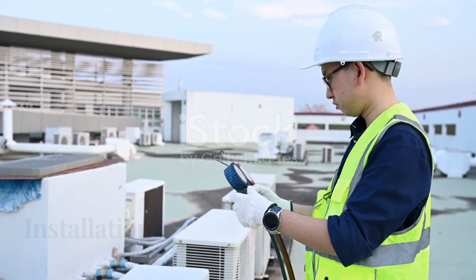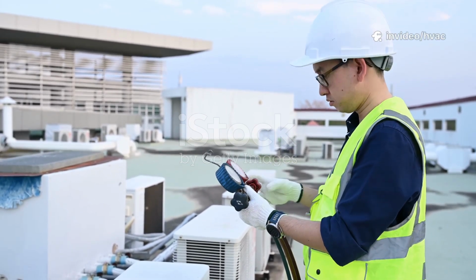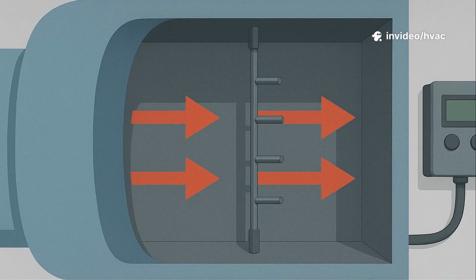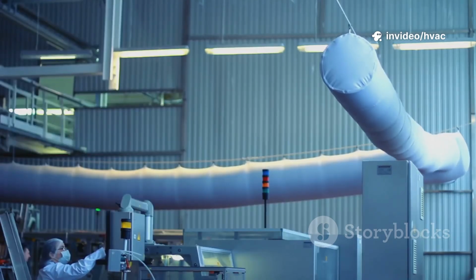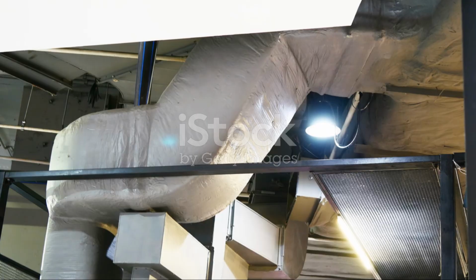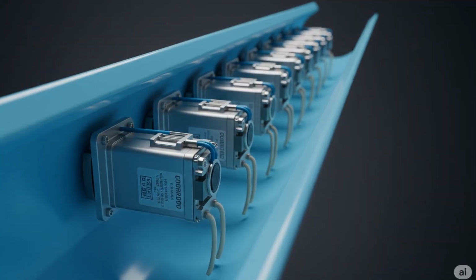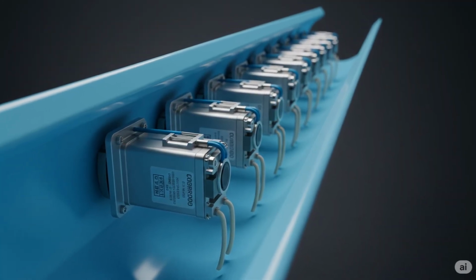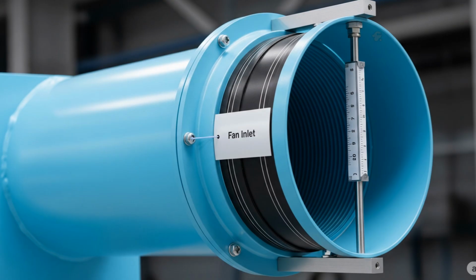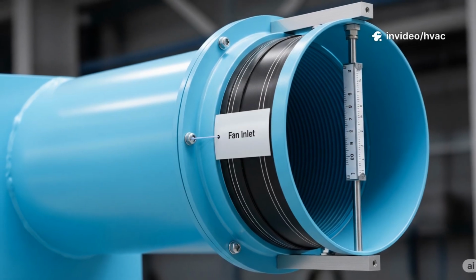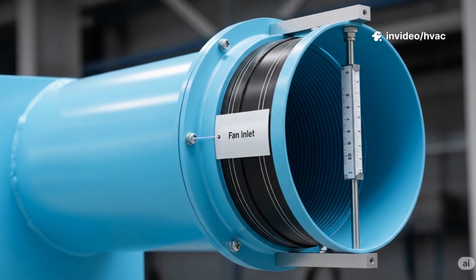Each airflow measurement system has its own set of pros and cons. Pitot arrays, for example, are pretty simple to use, but they really need clean, straight duct runs to work well. Thermal sensors, on the other hand, can fit into tighter spaces, but they do come with a higher price tag. And if you're using fan inlet measurement, just remember it needs factory calibration to be accurate.